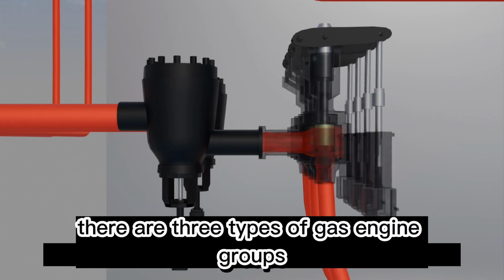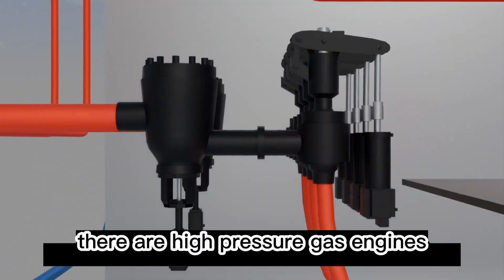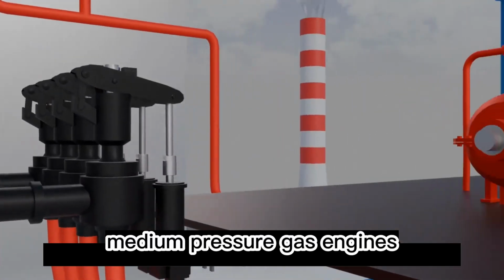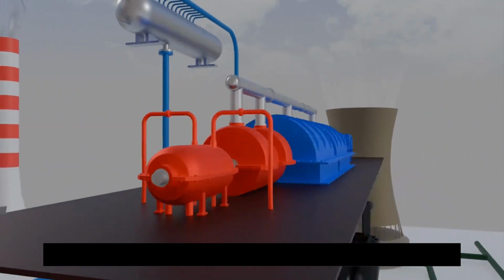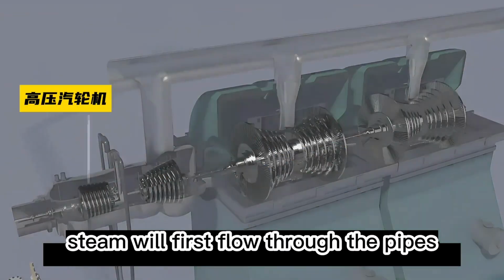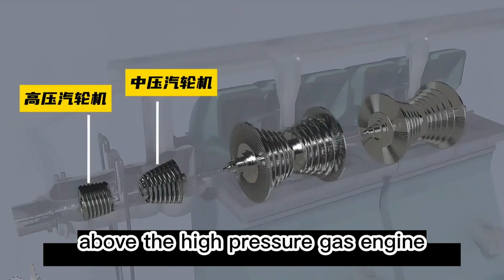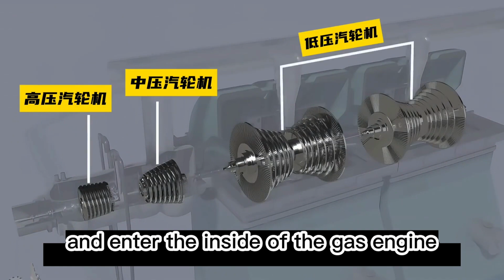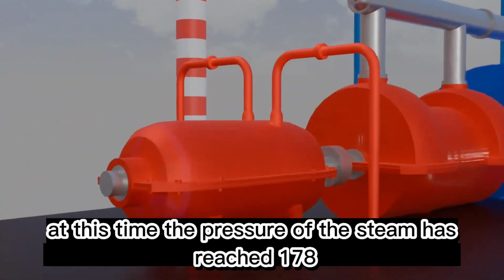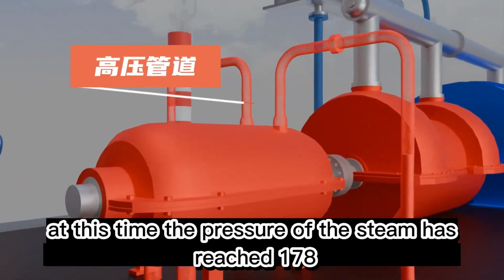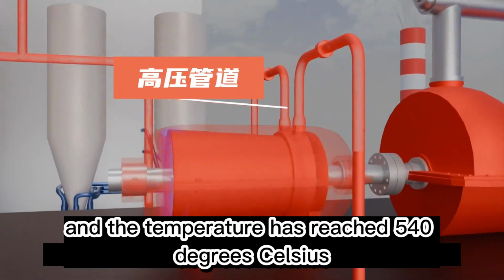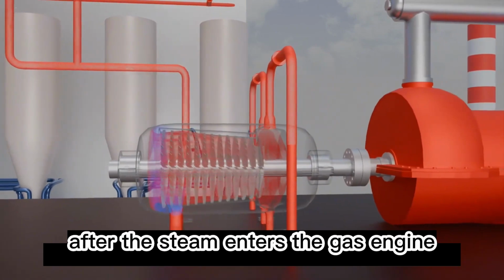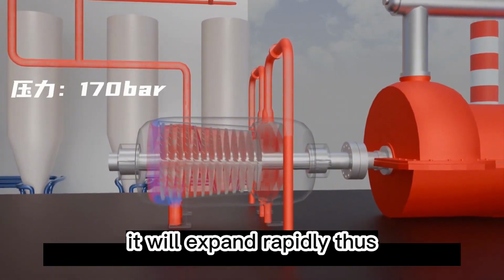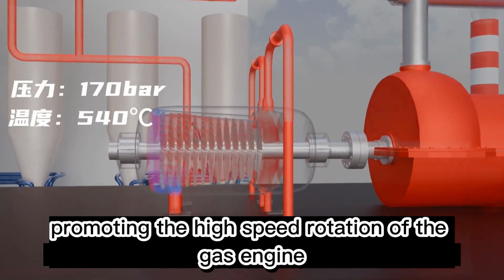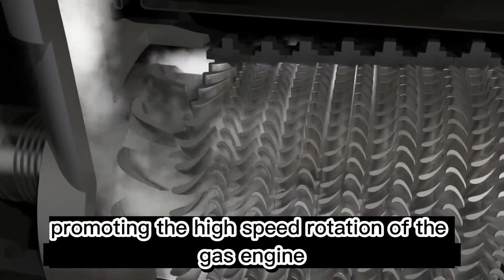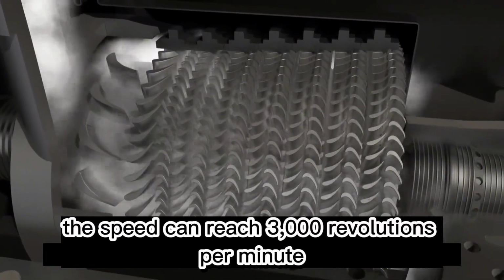There are three types of steam turbines. They are high-pressure turbines, medium-pressure turbines, and low-pressure turbines. High-temperature, high-pressure steam will first flow through the pipes above the high-pressure turbine and enter the inside of the turbine. At this time, the pressure of the steam has reached 170 bar and the temperature has reached 540 degrees Celsius. After the steam enters the turbine, it will expand rapidly, thus promoting the high-speed rotation of the turbine. The speed can reach 3,000 revolutions per minute.